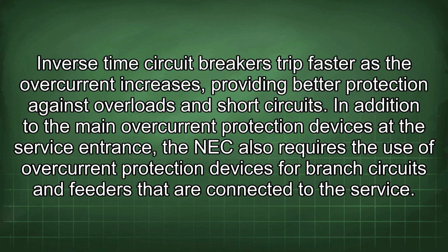Inverse time circuit breakers trip faster as the overcurrent increases, providing better protection against overloads and short circuits. In addition to the main overcurrent protection devices at the service entrance, the NEC also requires the use of overcurrent protection devices for branch circuits and feeders that are connected to the service.